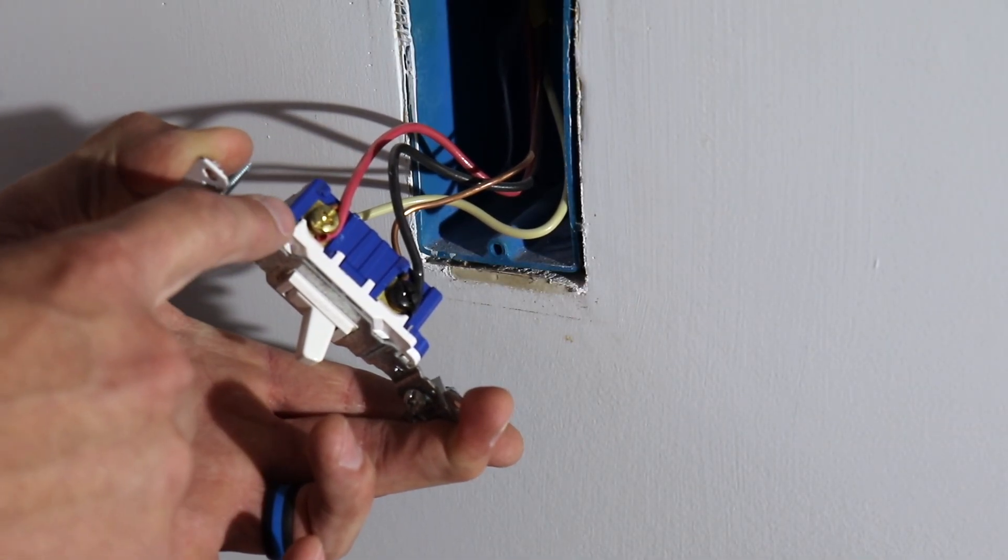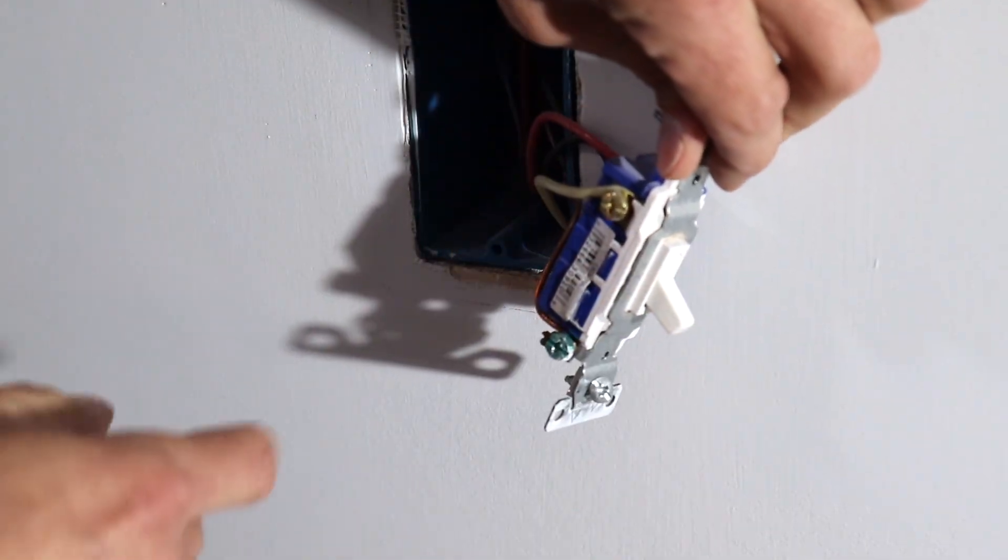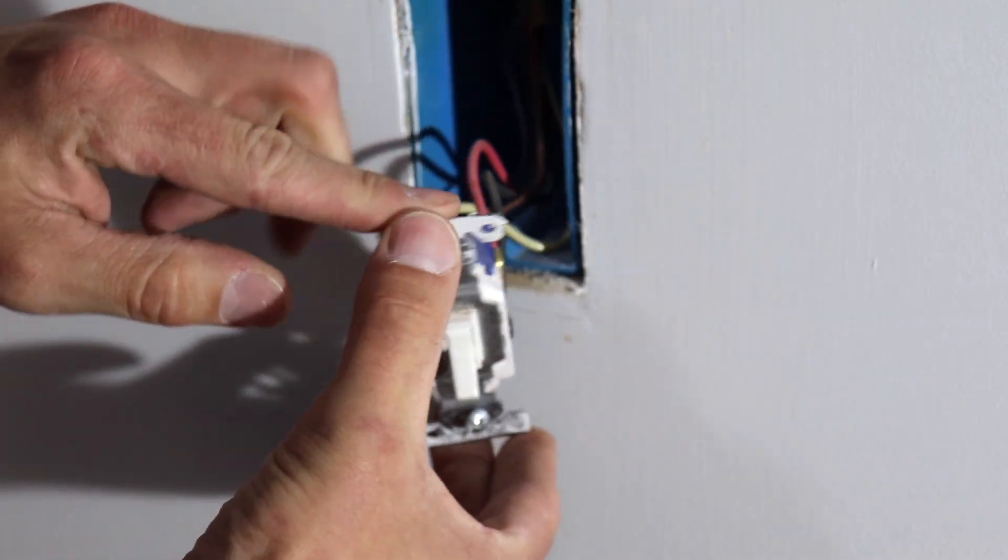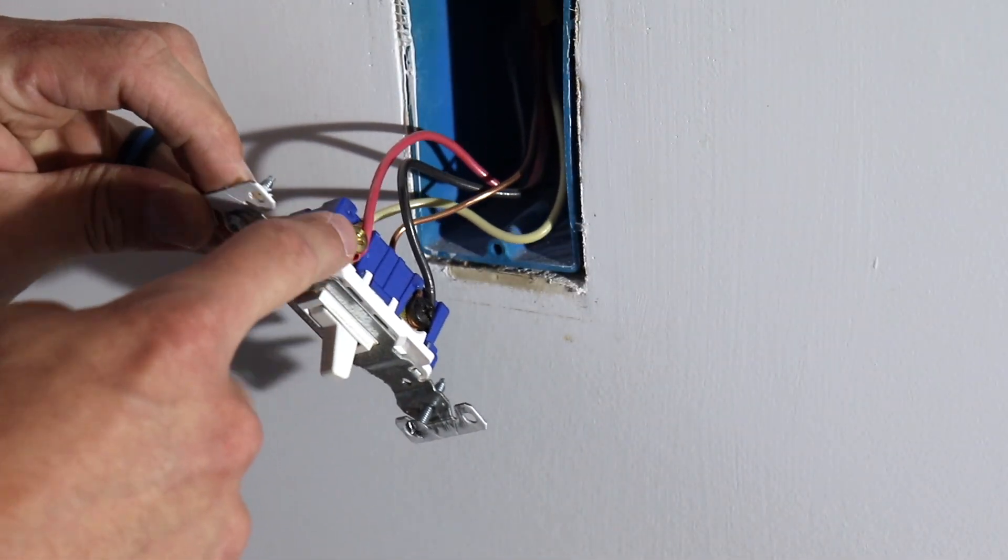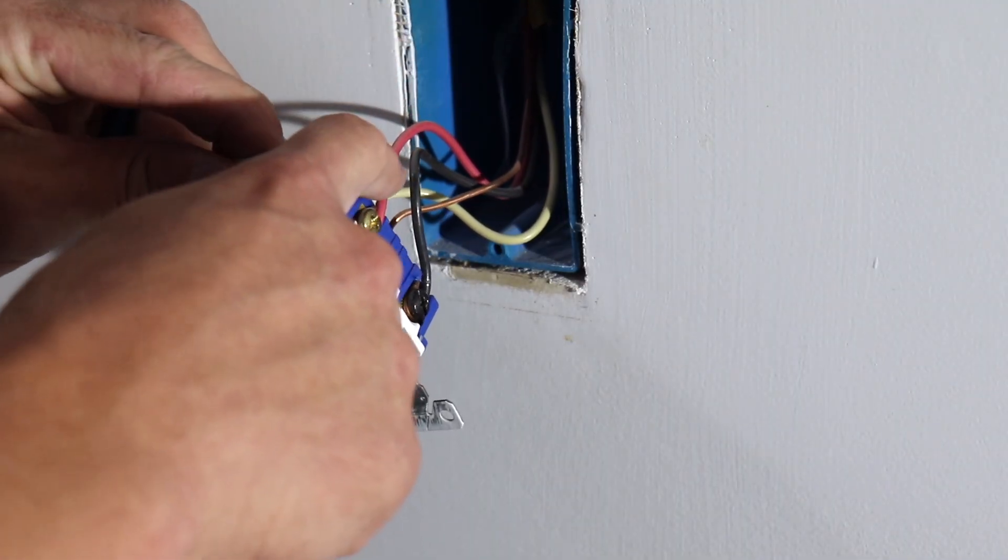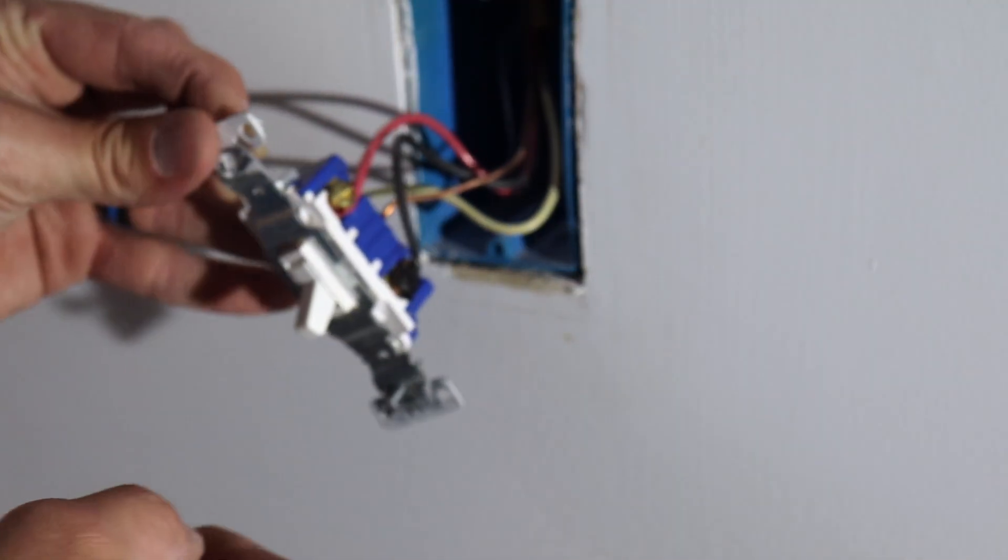We have a red wire going to this brass terminal on this side. Now on this side of the switch, we have a white wire going to this brass terminal. These top two that are connected to the brass terminals are called your traveler wires. So these just provide power to and from both of the three-way switches.